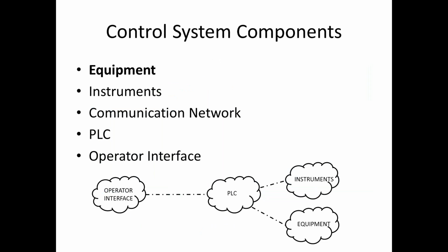So that was basically a control system, and we want to talk a little bit about the components. There's basically 5 components that any control system needs to deal with. There's equipment, instruments, there's the communication network, there's the controller, and then there's the operator interface. And as you can see by the schematic below, both the instruments and equipment are wired directly up to the programmable logic controller, and it is responsible for all the control systems that go in. And then it relays that information to the operator interface so the operators can view and monitor and take control if they need to. We'll talk a little bit about all of these components throughout this presentation.